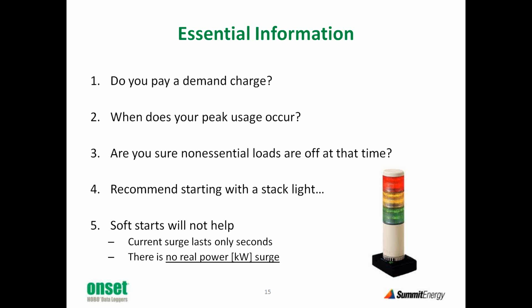So my recommendation is to start with a simple stack light like this and have a meter or a little controller that lights the green light when there is no possibility of setting a peak, light the yellow light as you're approaching a peak, and the red light when a peak in fact has been reached, and put 2 or 3 of those stack lights around the area so people can just be aware. When they see the yellow light, just think, is there something you could turn off? Are you getting ready to start some process that could wait 30 minutes or an hour? So that's my recommendation for a practical start.